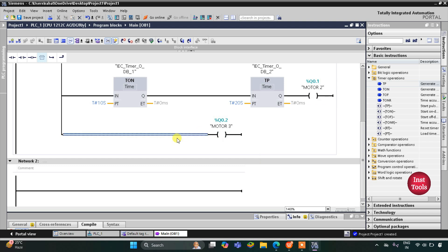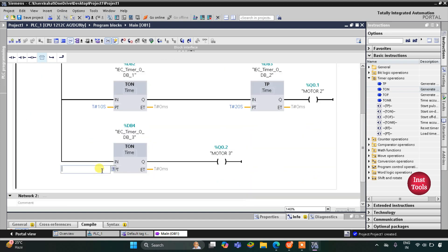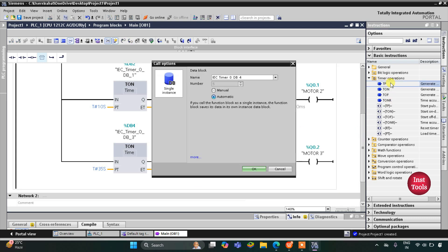Motor 2 should remain on for 20 seconds, so I'll insert a TP pulse timer for Motor 2 with a preset value of 20 seconds. After that, Motor 3 should get on when Motor 2 turns off — there will be a delay of 35 seconds total — so I'll insert a TON on-delay timer with a preset value of 35 seconds. Then Motor 3 should remain on for 15 seconds, so I insert another TP pulse timer with a preset value of 15 seconds.